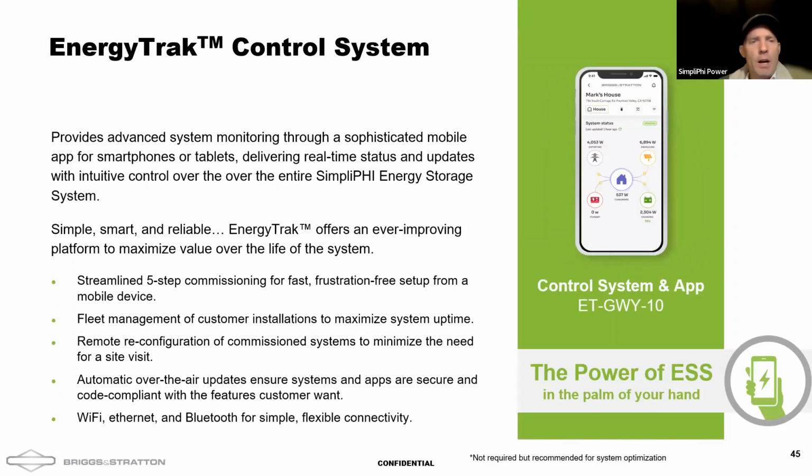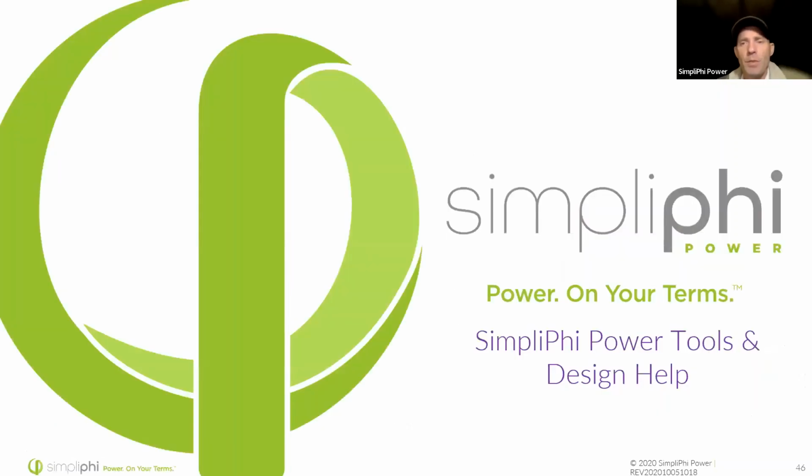And so the EnergyTrak app allows you to do a very fast commissioning process. I've heard from distributors that the Enphase systems are sometimes taking hours to do their commissioning process. We're able to use this to do a 5-step commissioning process, which includes setting up your homeowner's EnergyTrak account, right? And we've gotten that down to about 12 minutes for commissioning. So it's a really quick way to commission a system. You can connect to the gateway through Bluetooth, Ethernet, or Wi-Fi. So we've got some flexible connectivity there as well.